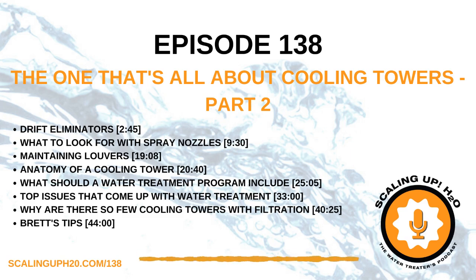Fair enough. Whether we're treating it or we're the manufacturers of what we're treating, we have to deal with corrosion, scale, microbial fouling, and the dirt and debris coming into the system. That doesn't change no matter where you are on the fence. All of the equipment manufacturers, us and the competitors, give water chemistry parameters based on the materials of construction selected. This is a table I'm looking at right now. It has properties like pH, conductivity, alkalinity, calcium hardness, and chlorides. And then, if it's galvanized steel, 304, or 316, the recommended ranges to keep that water chemistry in.